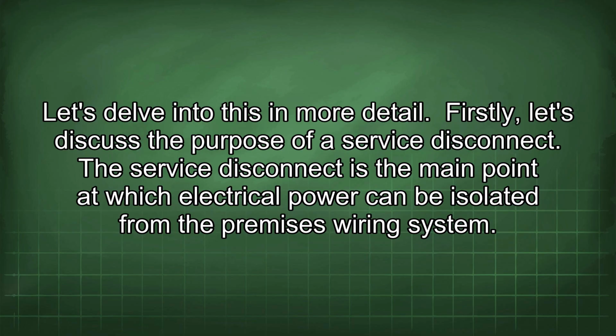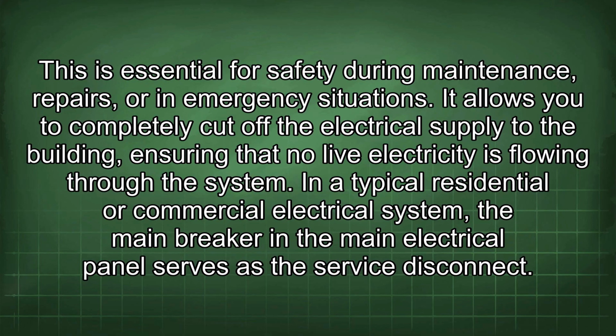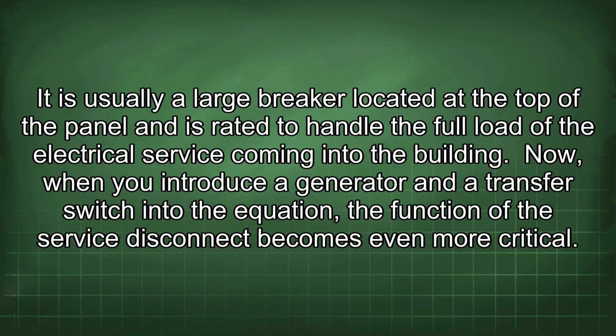Firstly, let's discuss the purpose of a service disconnect. The service disconnect is the main point at which electrical power can be isolated from the premises wiring system. This is essential for safety during maintenance, repairs, or in emergency situations. It allows you to completely cut off the electrical supply to the building, ensuring that no live electricity is flowing through the system. In a typical residential or commercial electrical system, the main breaker in the main electrical panel serves as the service disconnect. It is usually a large breaker located at the top of the panel and is rated to handle the full load of the electrical service coming into the building.